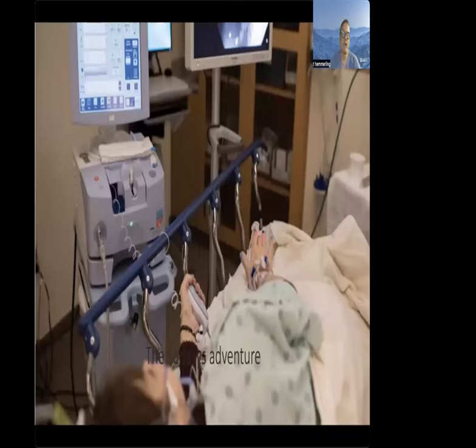There were several problems with this overall very appealing and absolutely necessary device. One limitation, for example, was that the Sedasys system was only able to decrease the propofol dose and not increase it automatically; any increase needed to be effectuated by the physician. It also took considerable time to achieve a certain degree of sedation, which was quite problematic given the fast pace of a busy endoscopic suite.